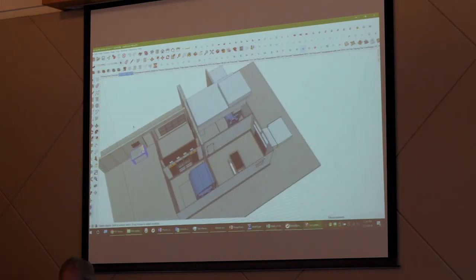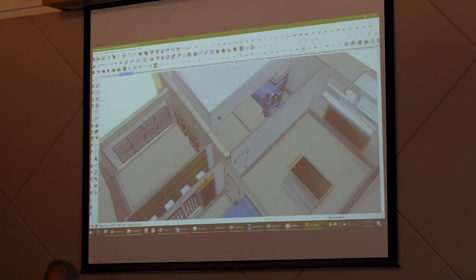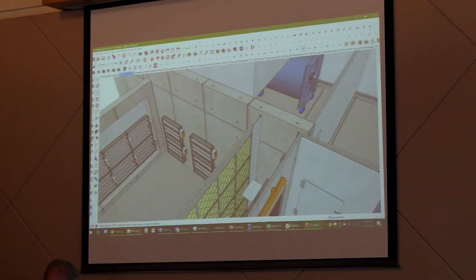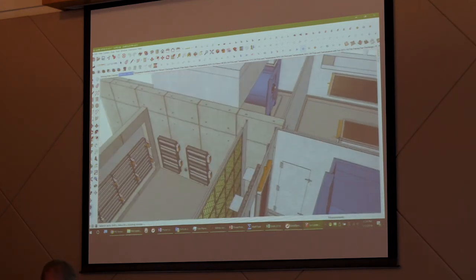So, built back when they weren't worried about energy, right? And at the time, it was a 100% outdoor air system. But the physics building was mostly offices. There were a couple labs that had some hoods, but it was mostly offices. And so I don't really know this, but the evidence would suggest that during the energy crisis, somebody said, there's got to be a better way to do this than 100% outdoor air. And so they took the relief fan, built a plenum, dropped a couple ducts out of the plenum, cut some holes in the wall, and put return dampers in, and they built an economizer. Okay?